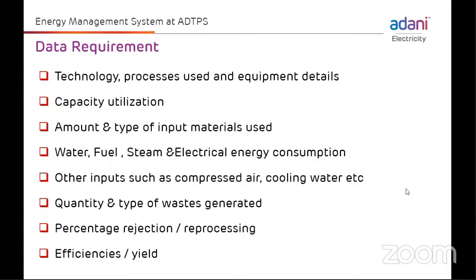Then the amount and type of input materials used - what type of materials you are using. For example, we use coal as the main fuel in boilers. If we use coal with a higher ash percentage, most mechanical students know that the air input required in the boiler for combustion will be high. But the output will remain the same. Handling that air or flue gas requires higher fan loading, which ultimately increases auxiliary power consumption.